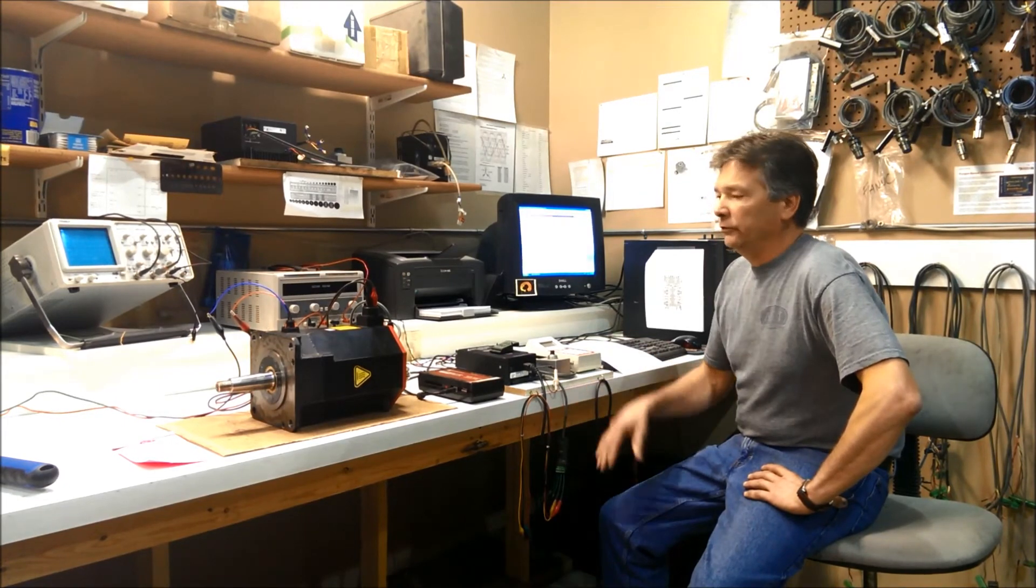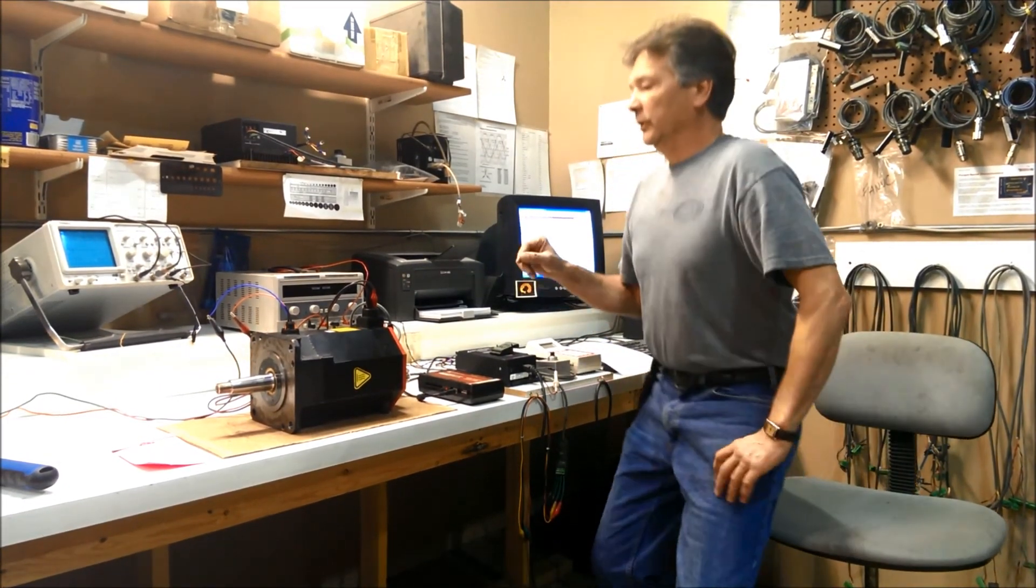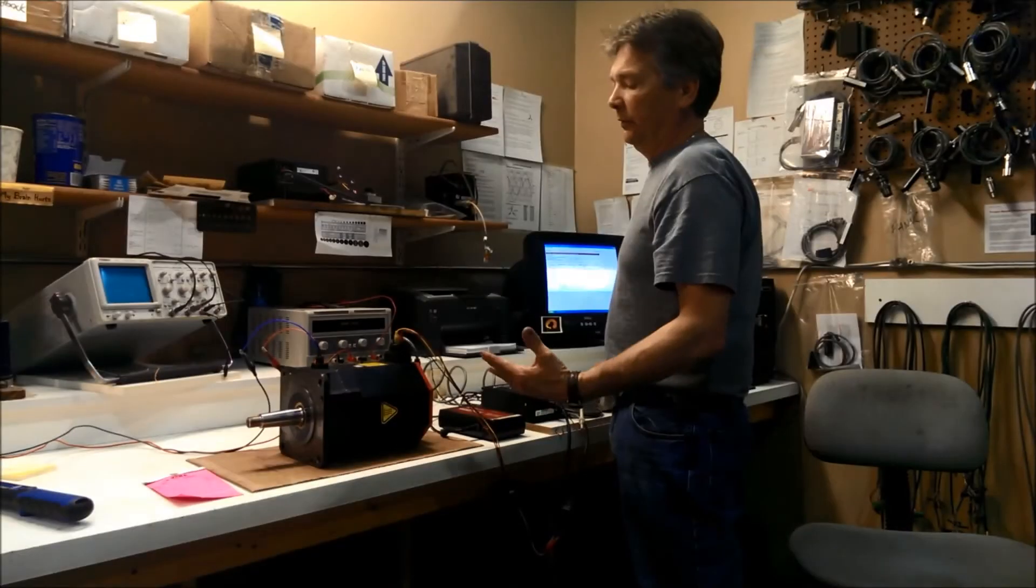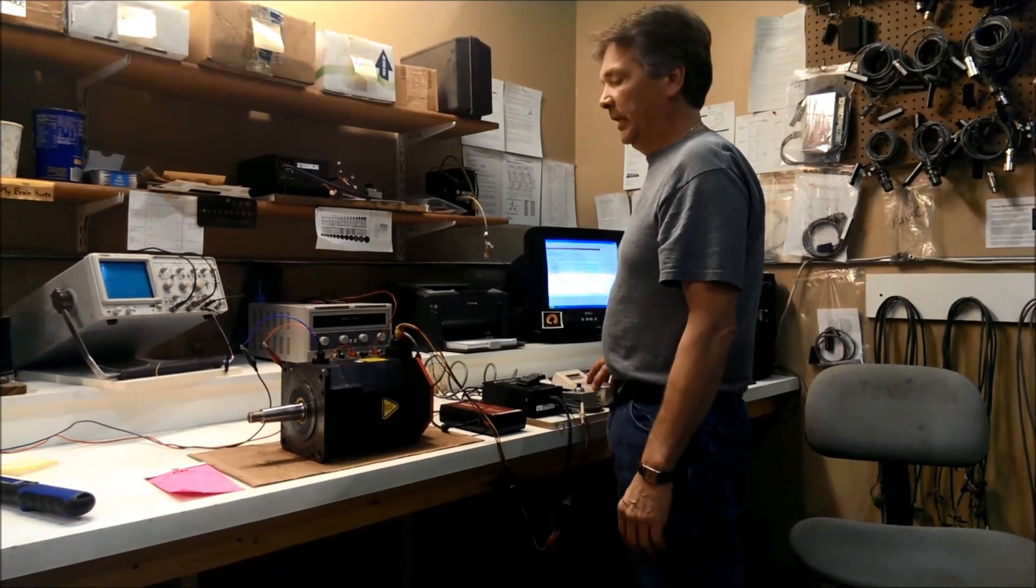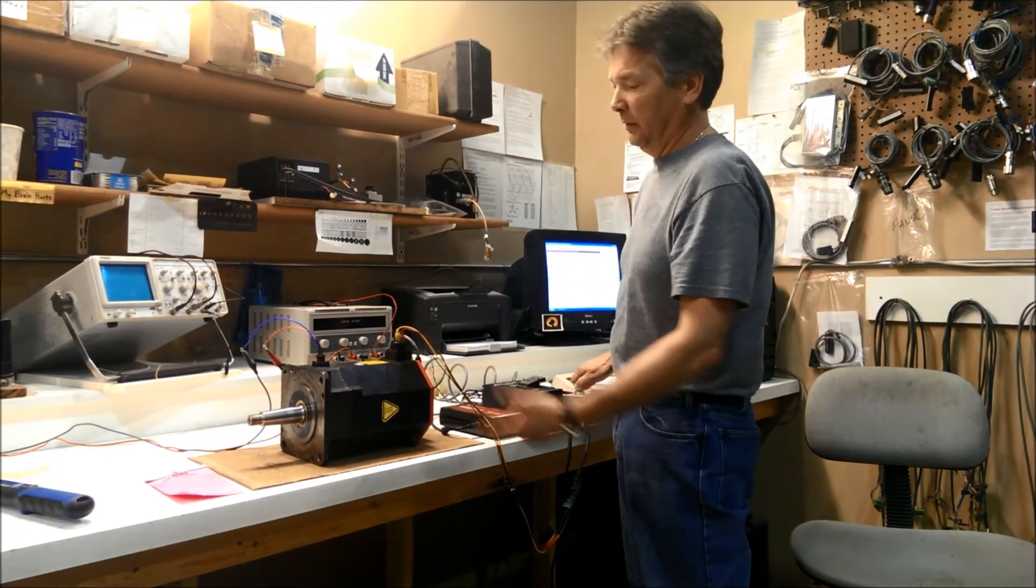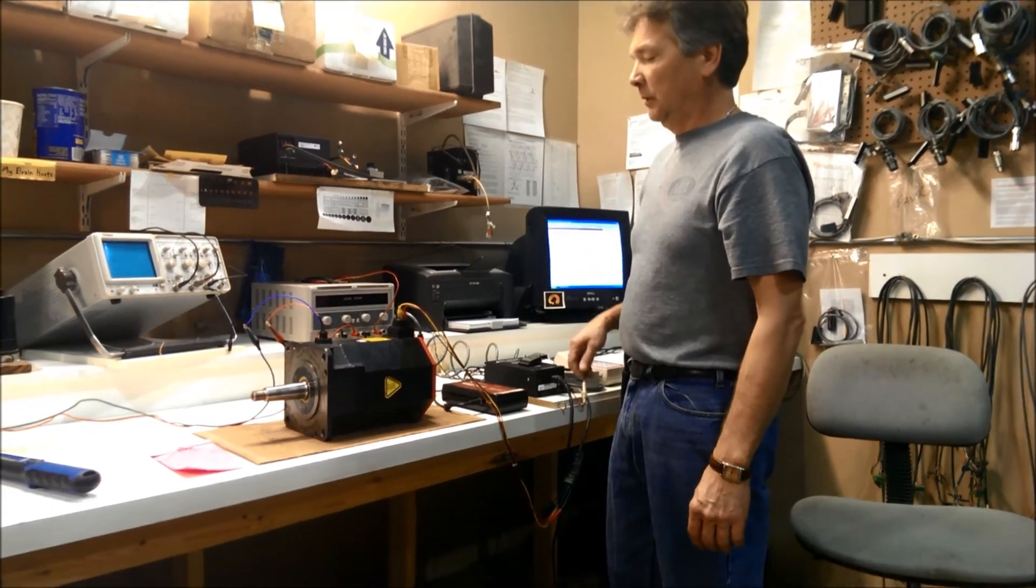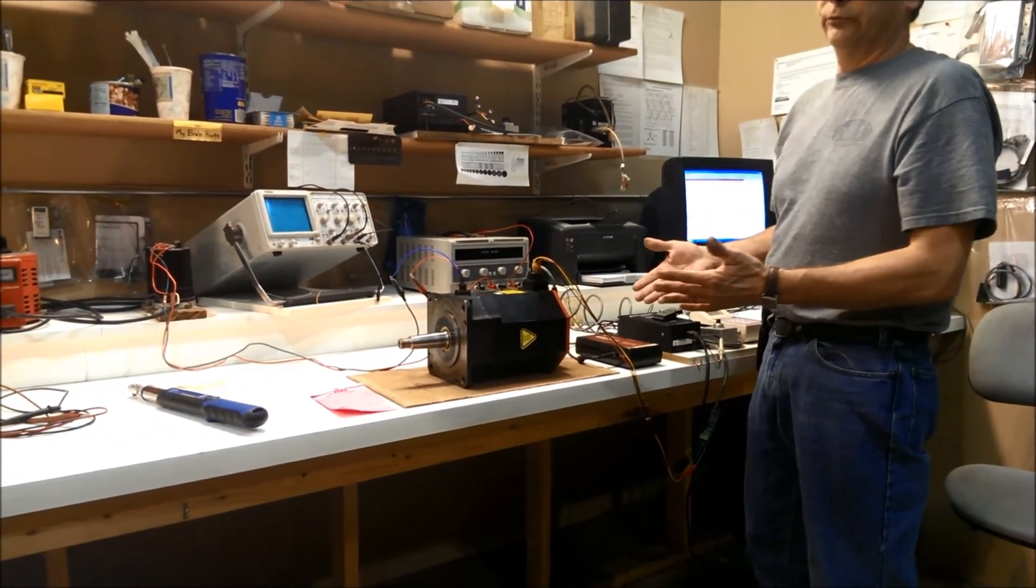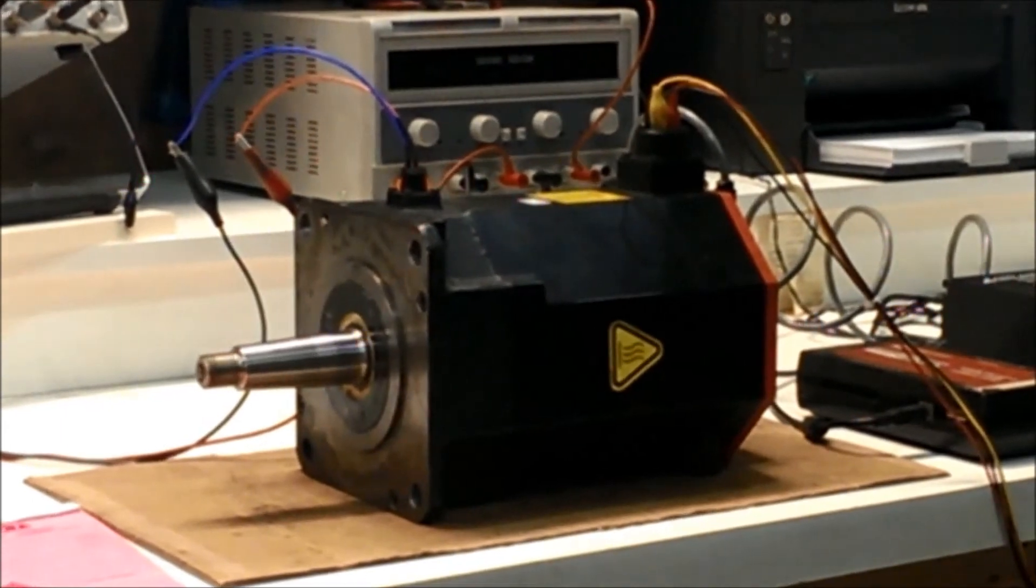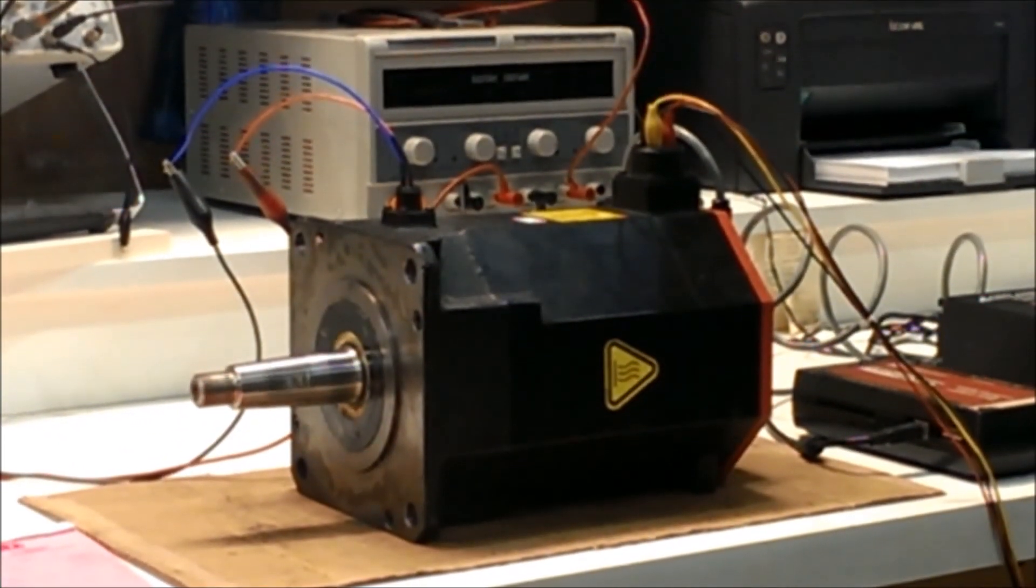I can also use the TI 3000 to actually run the motor and we'll do that real quick. The TI 3000 will allow us to run the motors without actually having to have a FANUC drive in place. As you can see, when we finish repairing the motor we'll align the encoder and then we will actually do a test run of the motor and make sure it's operating properly. As you can see, the shaft on the FANUC motor is turning.